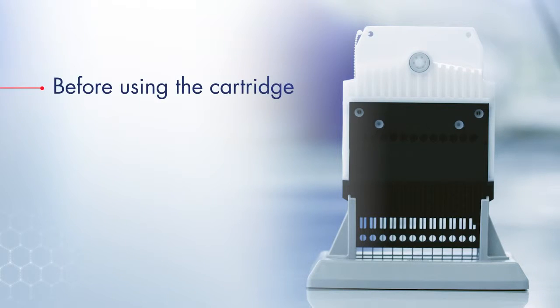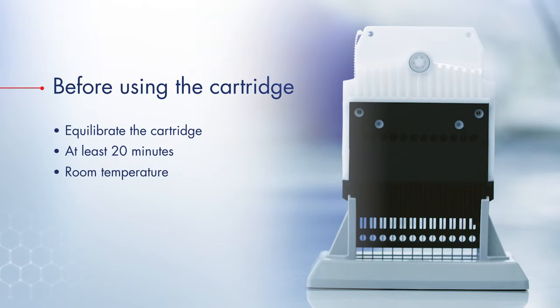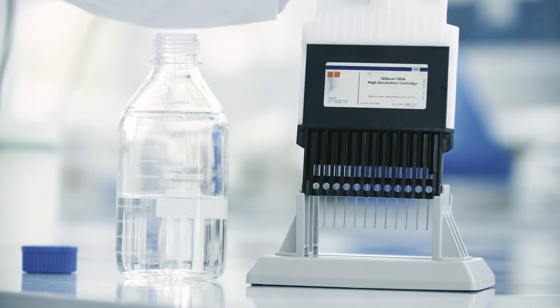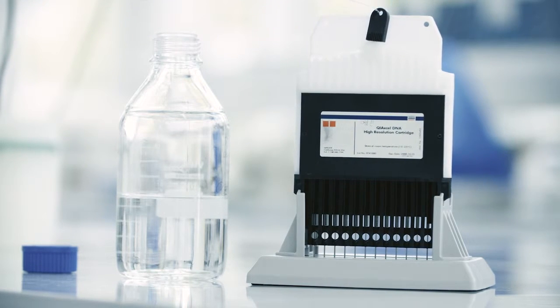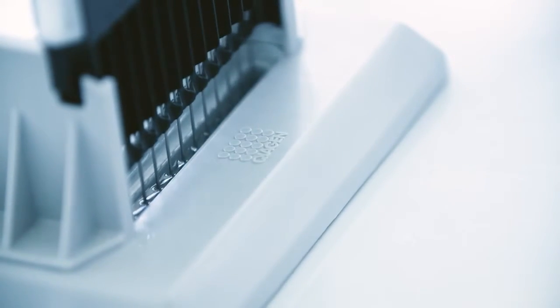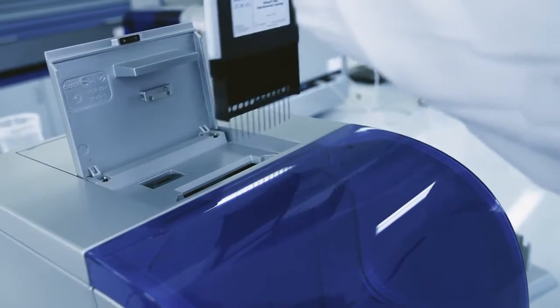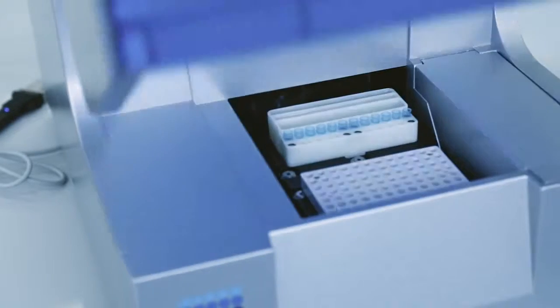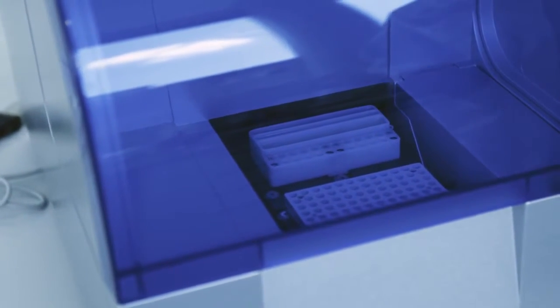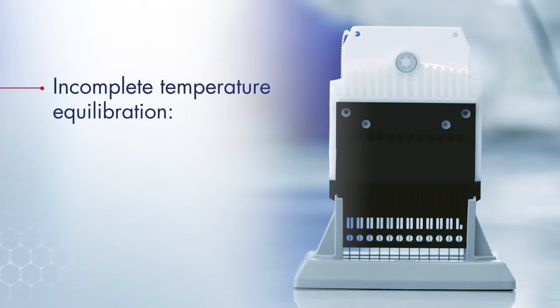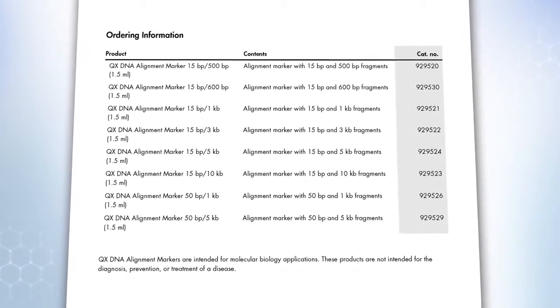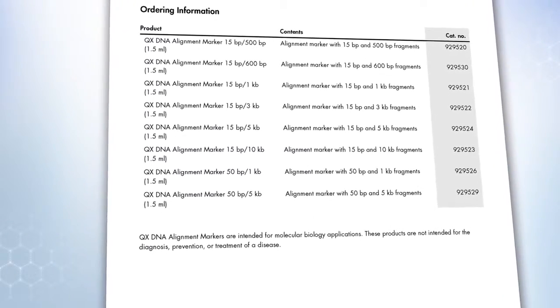Before using the cartridge, it is crucial to equilibrate the cartridge for at least 20 minutes to room temperature to ensure proper analyte separation. To equilibrate the cartridge, either place it into the cartridge stand, including wash buffer overlaid with mineral oil, or directly place the cartridge into the QIAxcel Advanced. Ensure that the buffer tray is loaded and wait. Incomplete temperature equilibration can cause run problems and potentially also lead to instrument damage. Always use the correct cartridge type together with the appropriate buffers and markers.